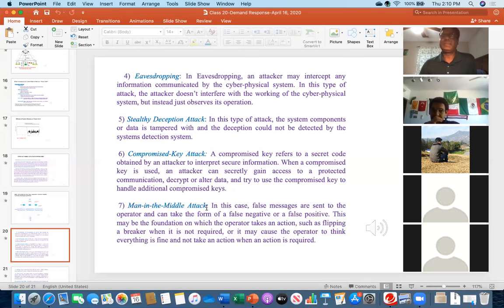Man in the middle attack: false messages are sent to the operator, taking the form of a false negative or false positive. Going back to the circuit breaker example, it's running well, and suddenly, in the middle of operation, someone sends a bad signal. The protective relay system gets a message saying there's a fault on the line, so it opens, which is not true. Or the circuit breaker opened for a valid reason, a real fault, and it's not yet time to reclose because you have to allow some time, but a bad signal is sent and received, saying close now, so you close the breaker - that will also destroy the system. It's like hampering the operation midway. That is called man in the middle attack.